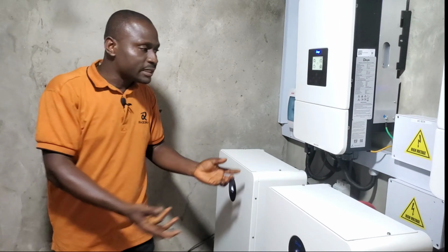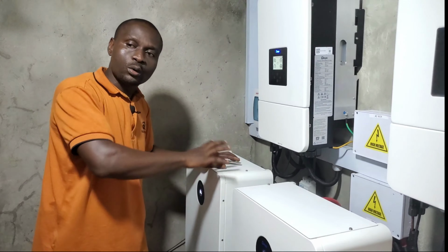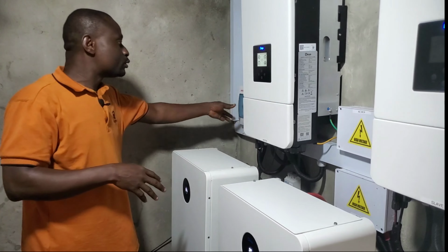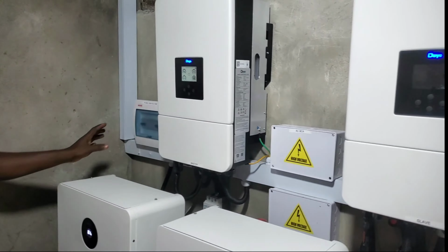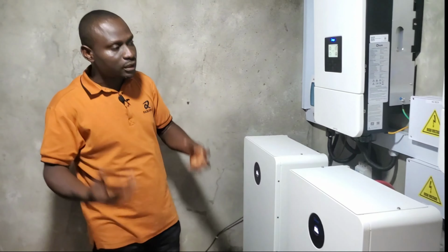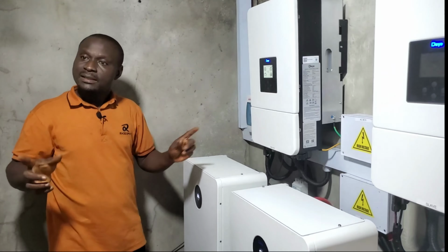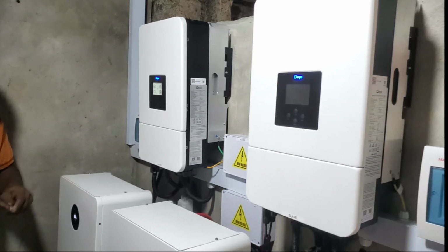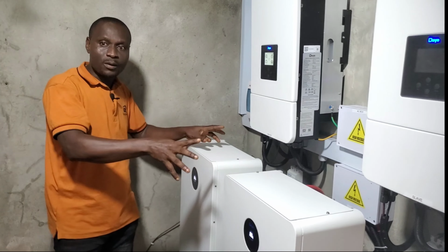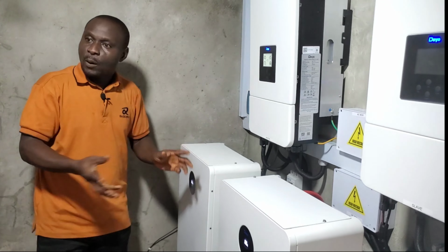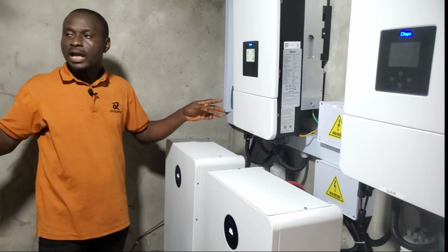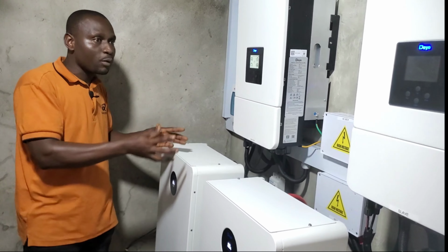So you calculate these things according to the current that passes through them. Here they use the size of these cables to match the size of these breakers. So all these things must work together so that your solar system will give you what you need. If you don't do these things well, your solar system may go off even when the sun is shining. At times when the sun is high, you will see your system shout and go off because you did not size your things very well. Sometimes at night, when you need light with battery, things go off. The inverter goes off or the battery just goes off. It will tell you no battery because you did not check those things very well before you used them.